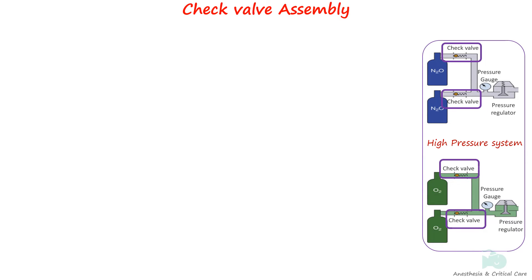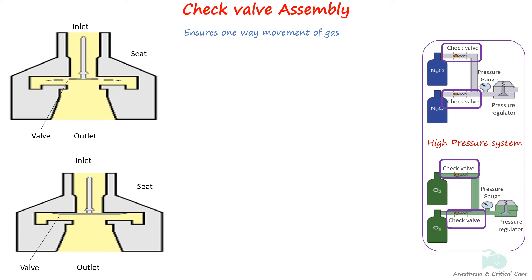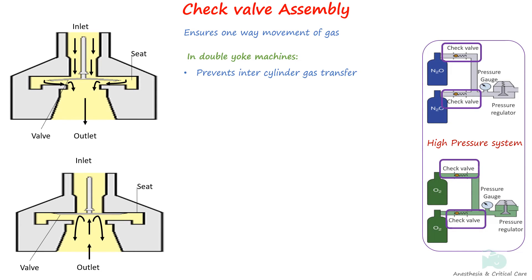The check valve assembly allows gas to enter the machine but prevents gas from exiting the machine when there are no cylinders on the yoke. The valve consists of a plunger that slides away from the side of greater pressure, thereby occluding the orifice through which the gas flows. As the gas enters the check valve assembly, it causes the valve to move away from the seat allowing the gas to pass through. When the pressure or flow is reversed, the valve is pushed against the seat preventing gas entry. In a double yoke machine, it also prevents the transfer of gas from the cylinder with high pressure to the one with low pressure, and it allows for changing the cylinder without having to unmount the in-use cylinder.